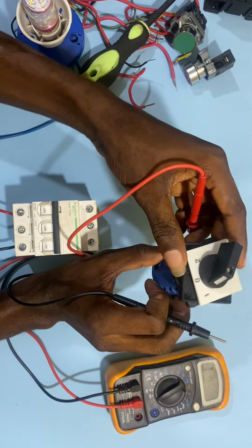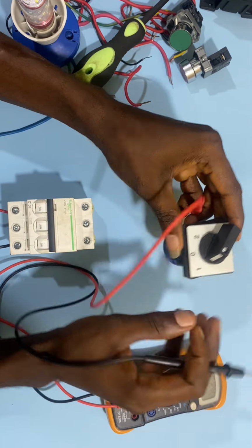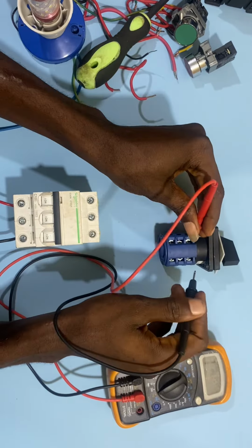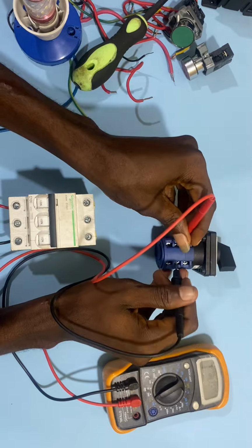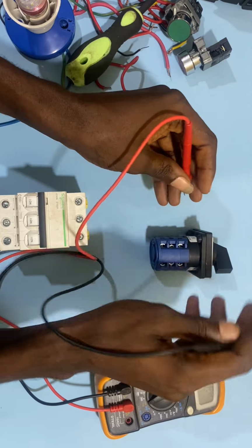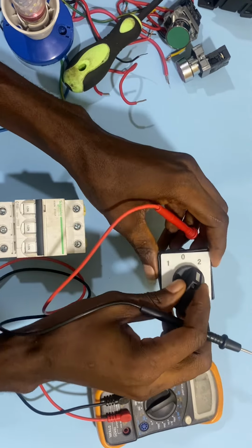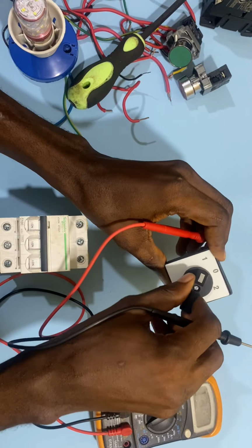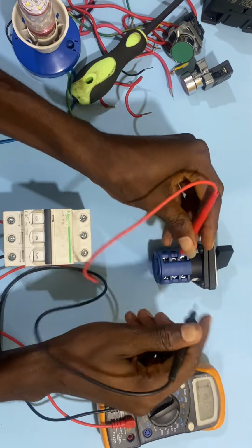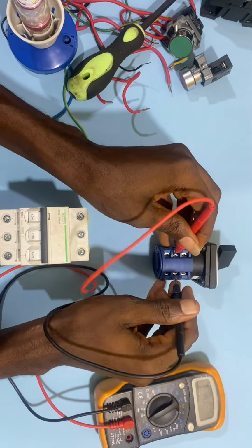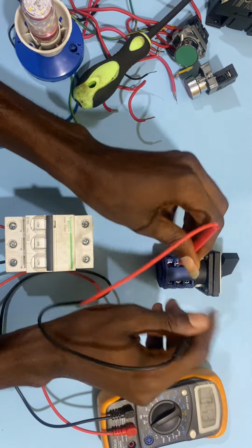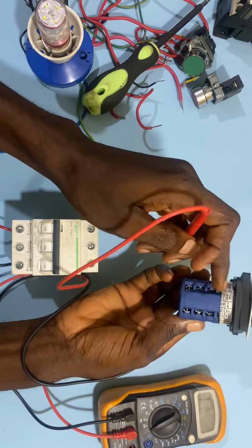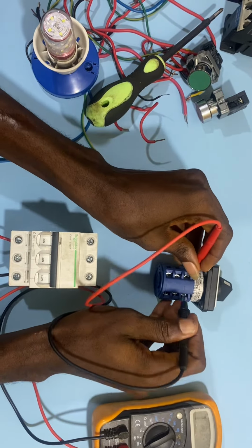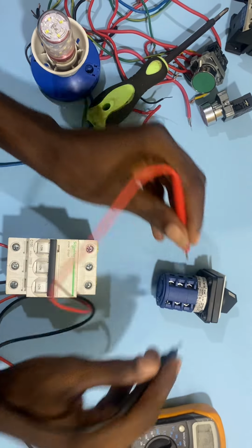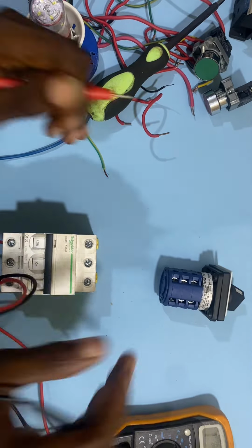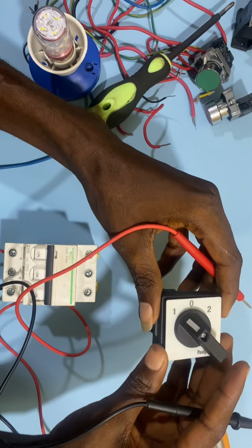But when it is at one position, if I turn it to this other phase, you see that this side is isolated. No way is connected at this point until I turn it back to the two position. No, it's at one position now. So if I turn it back to the two position, that is when this side is connected. Then if you turn to this other side, it will automatically be isolated. Let's see, it's isolated. Good. So this is how the switch J is operating.